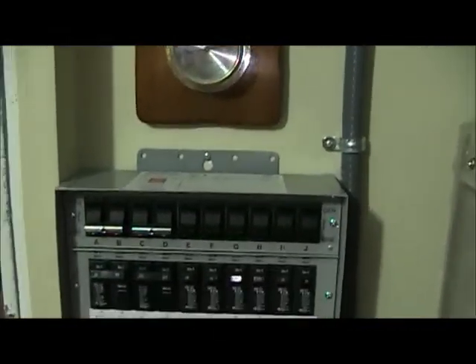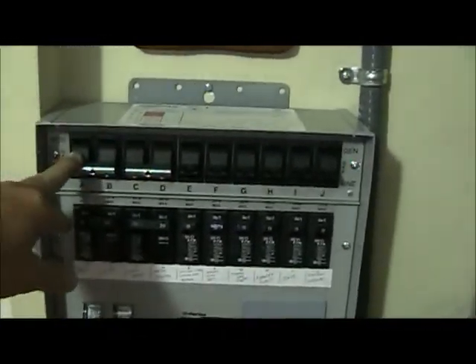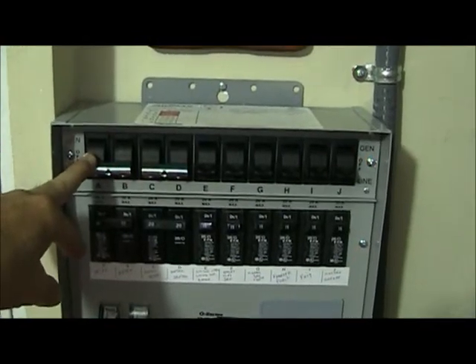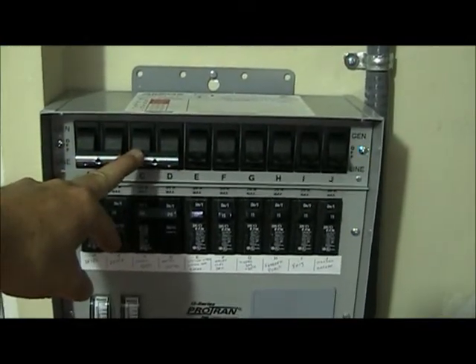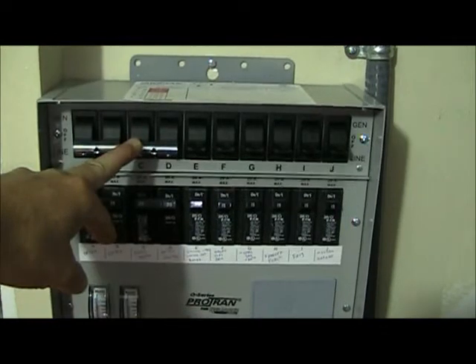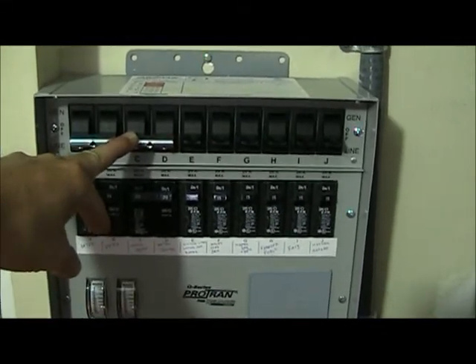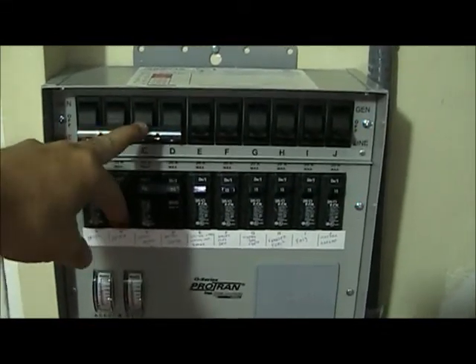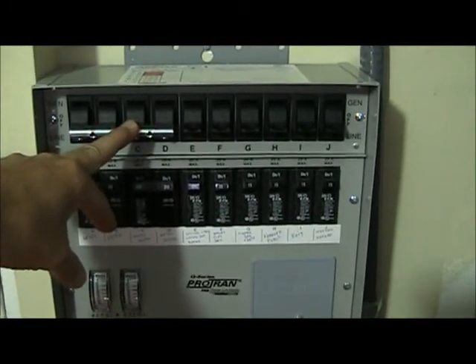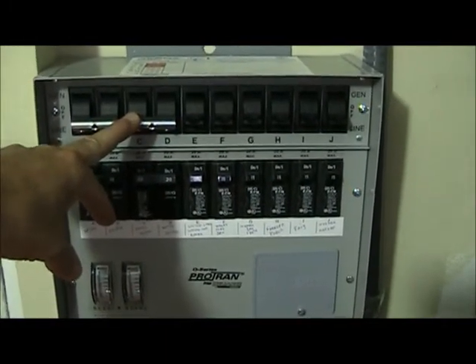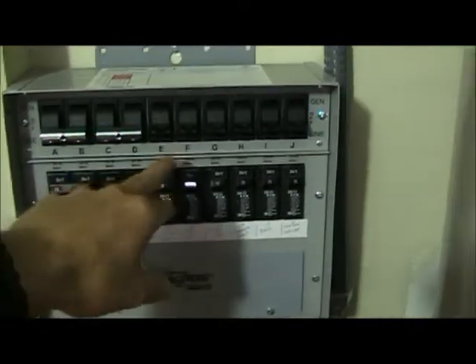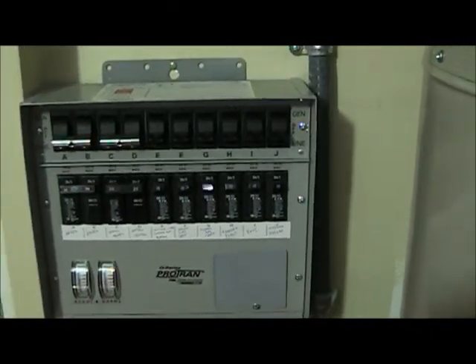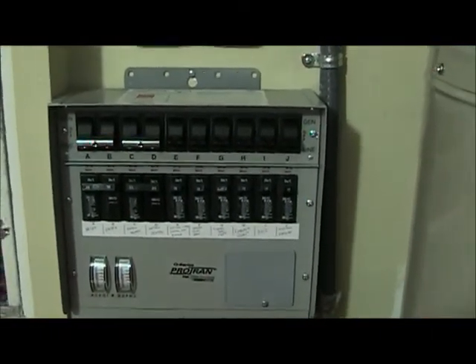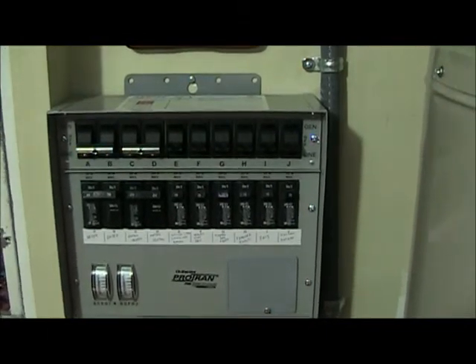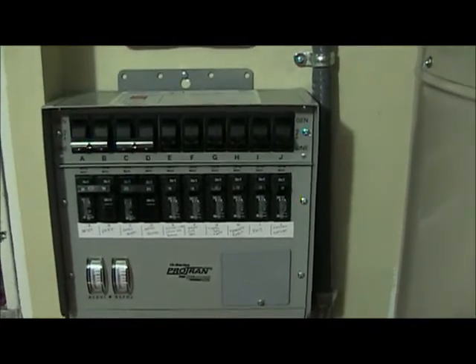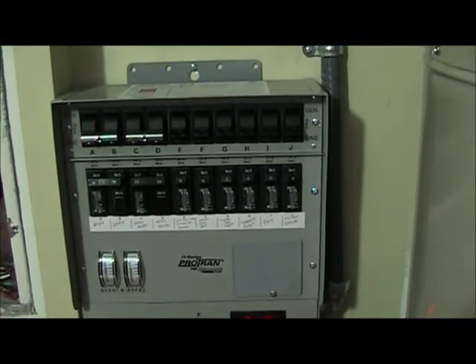What I can do here is, on this one I have the range connected - it's a 30 amp double pole. This is a 20 amp double pole that feeds the water heater. Most water heaters are fed with a 30 amp breaker, but when I was doing some testing, my hot water heater only drew about 18.5 amps per leg. The rest of them feed all the rooms in the house - the lighting, the ceiling fans, outlets in the bedrooms, and I have the refrigerator, freezer, and microwave on there.